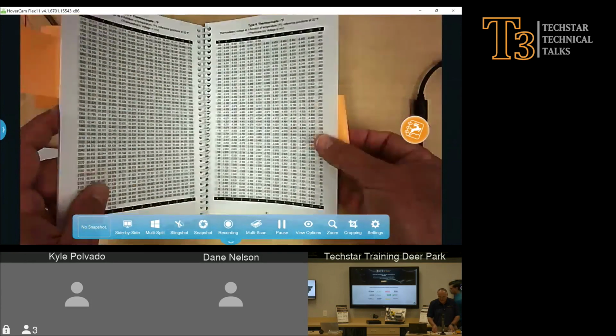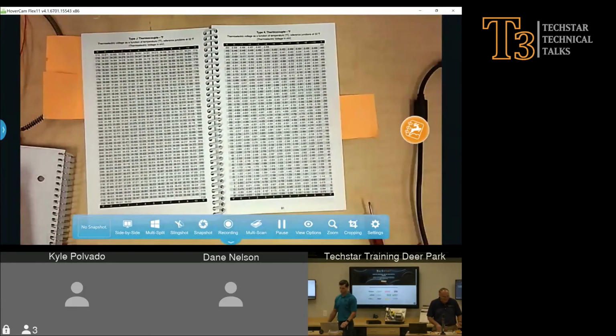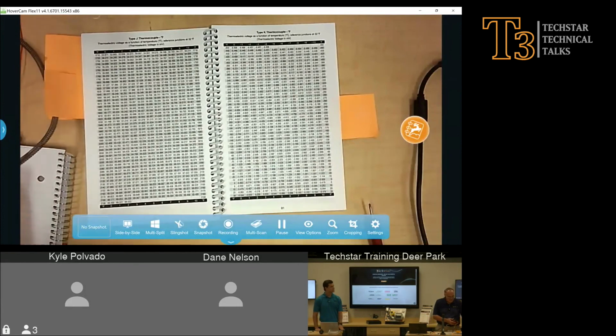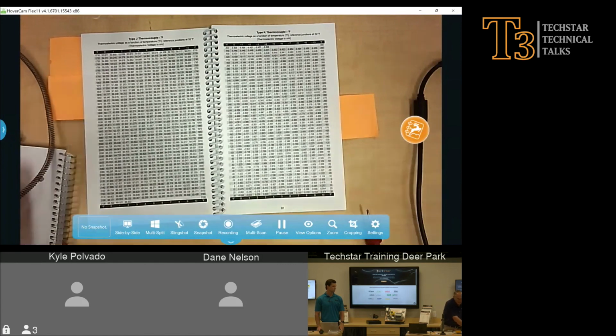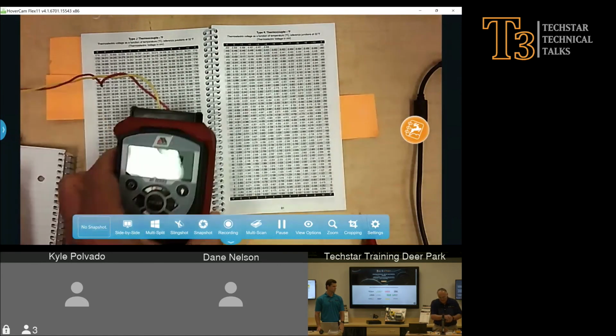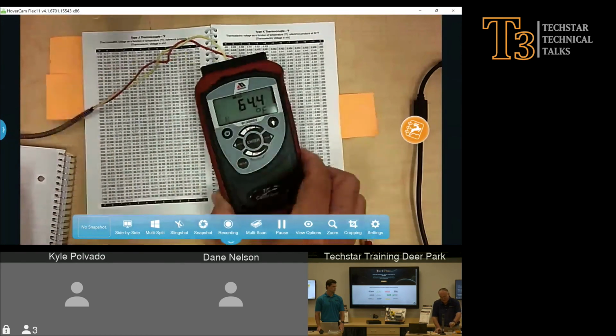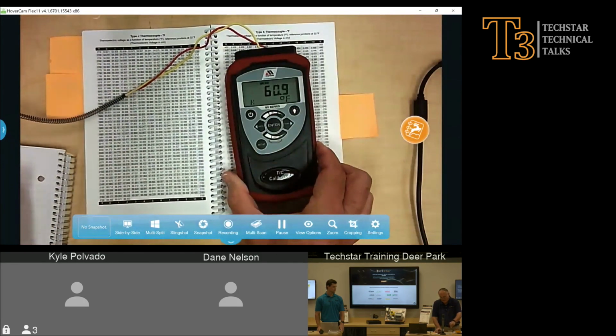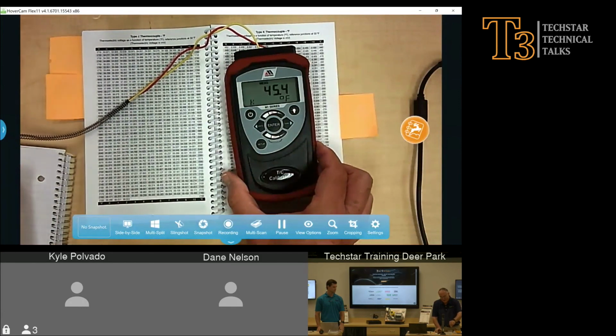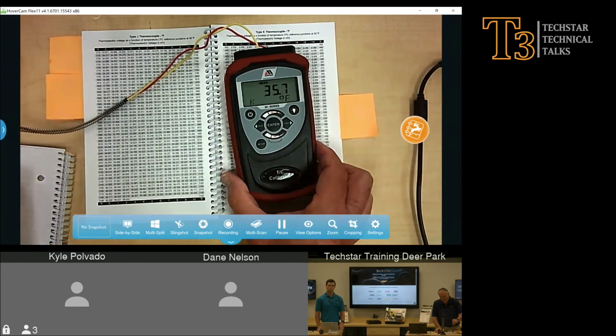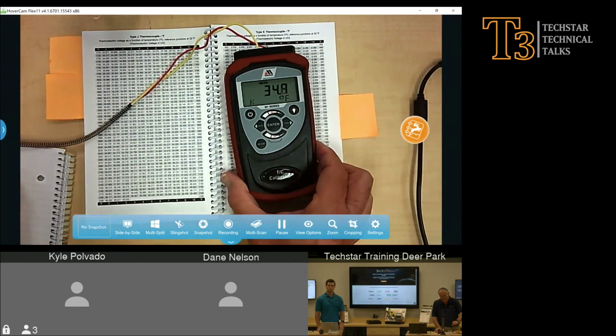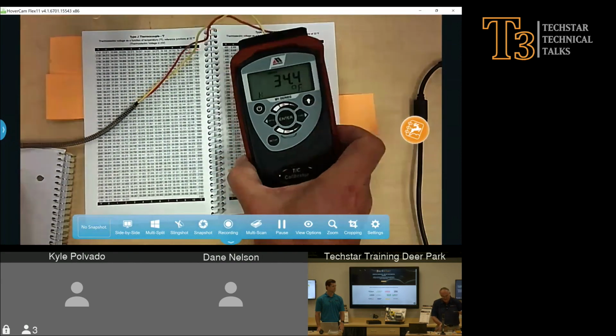Type J and type K thermocouples sometimes are a little bit harder to evaluate. You know, we had done that earlier, because you need a cold junction reference. If I had showed this one, so if I take this one in the box, whirl it around, again, this will also give you an idea of how fast these things respond. I've got them in there. Can you imagine putting it in a thermowell? If I put my voltmeter on there, I get absolutely nothing. So I hope that would help.